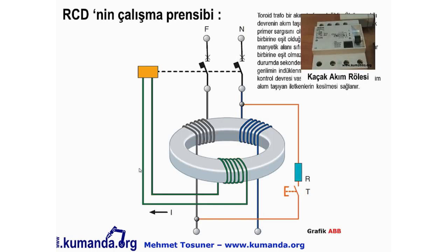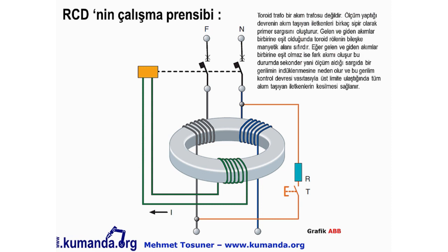RCD içerisinde bir toroid transformatör vardır; bu bir akım trafosu değildir. Akım taşıyan iletkenler toroidin primer sargısını oluşturur. Gelen ve giden akımlar birbirine eşit olduğunda toroidin bileşke manyetik alanı sıfırdır; sekonder sargıda gerilim indüklenmez. Eğer akımlar eşit olmazsa fark akımı oluşur, sekonder sargıda gerilim indüklenir; bu gerilim üst limitlere ulaştığında tüm akım taşıyan iletkenler kesilir.